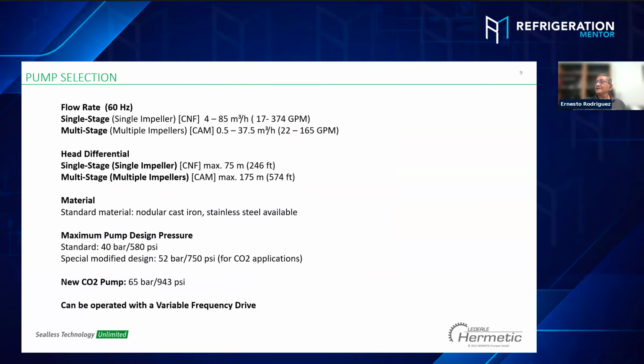Okay, let's go to the next slide. What is the difference between the one impeller and multi-impeller? Well, I can explain right here. One impeller pump is very good for mass flow. We can move more mass flow with one impeller pump versus the multi-impeller. Multi-impeller is not really good to move too much flow.